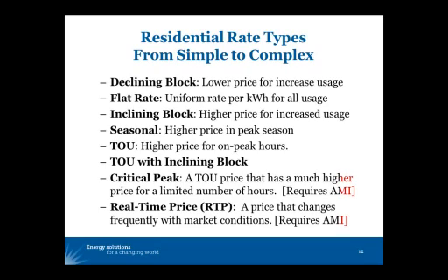So the first rate I'm showing is a relatively archaic rate design form, a declining block rate. This particular one is from Ohio. It has a $4.25 customer charge, which is about the cost of customer billing and collection. And then a rate for the first 800 kilowatt hours that covers most of the system costs. And then additional usage is priced at a lower rate because customers have already paid for most of the system costs.